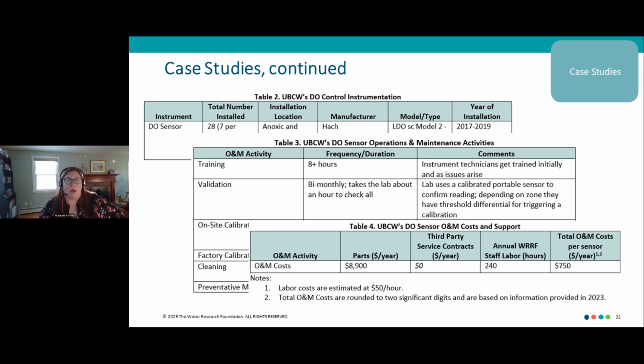Then it delves into the details of operation and maintenance: how much training have they done on it, how often do they validate? When we got to the case study versus the utility survey, we got a bit more granular on-site, looking at minor adjustments for calibration versus actually sending it back to the manufacturer. So there are two lines when we're talking about calibration in these case studies. Then how often they're cleaning, what that cleaning entails, and what preventative maintenance they're doing.